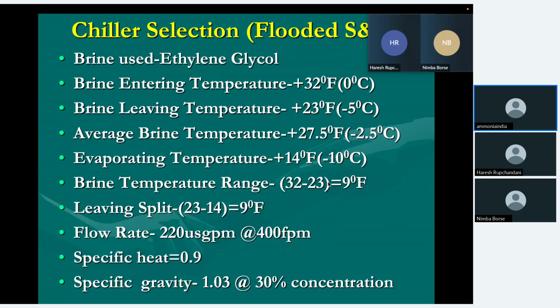The brine is ethylene glycol, 32 degree Fahrenheit inlet temperature, 23 degree Fahrenheit outlet temperature, mean temperature 27.5 degrees Fahrenheit, evaporating temperature 14 degree Fahrenheit. So brine range is 9 degree Fahrenheit and flow rate is 220 US GPM at 400 feet per minute velocity. Specific heat of brine is 0.9. Specific gravity is 1.03 at 30% concentration.